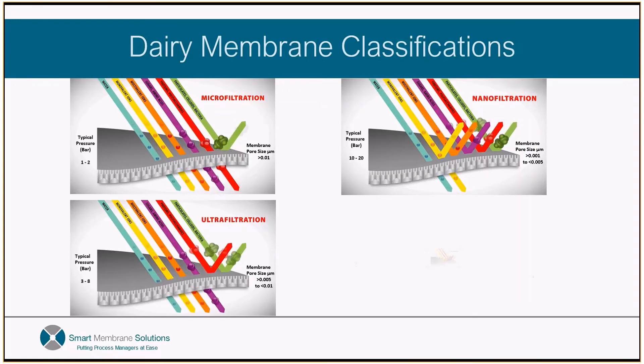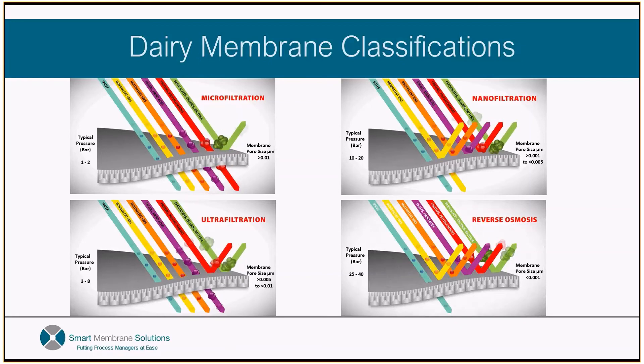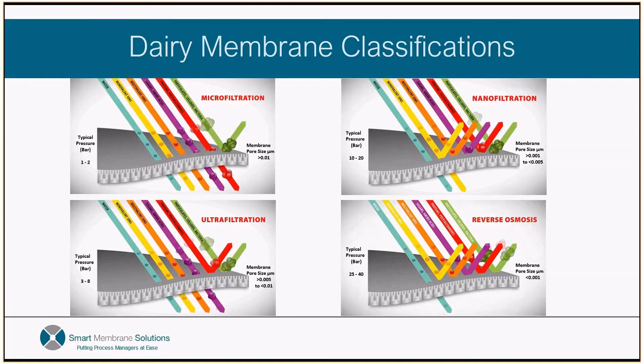Finally, we have reverse osmosis membranes, which effectively remove all organic and inorganic components from dairy streams to produce a membrane permeate that is essentially water with a small number of ions. In dairy, RO membrane systems run between 25 and 40 bar, which is 370 to 570 psi, and are used to concentrate whole milk, skim milk, as well as many whey and milk lactose permeates originating from milk, cheese, and casein whey UF processes.